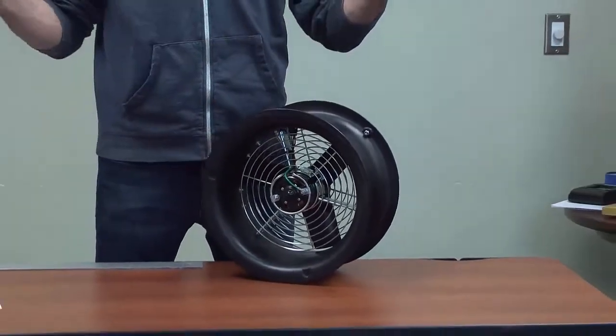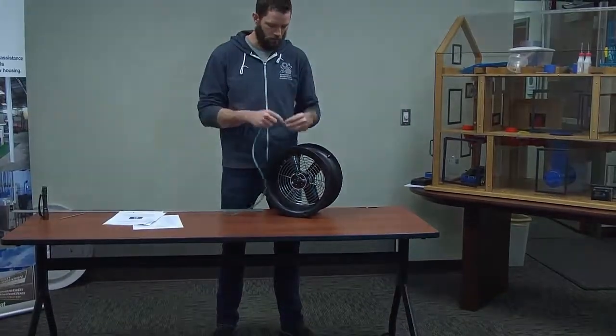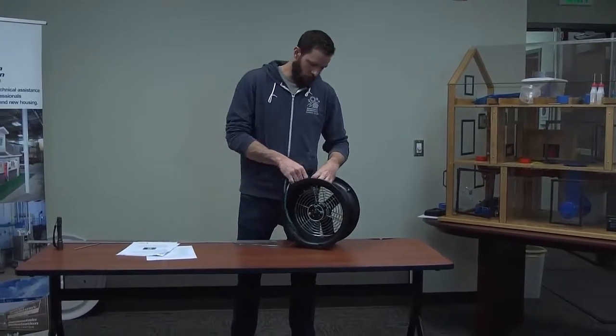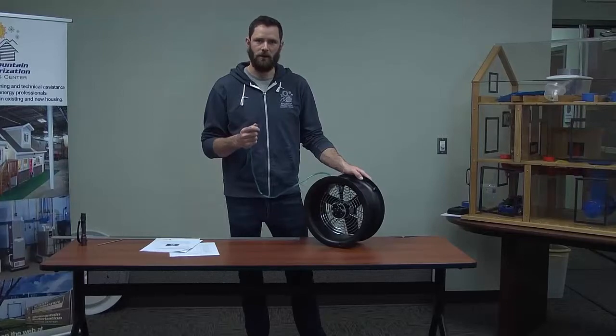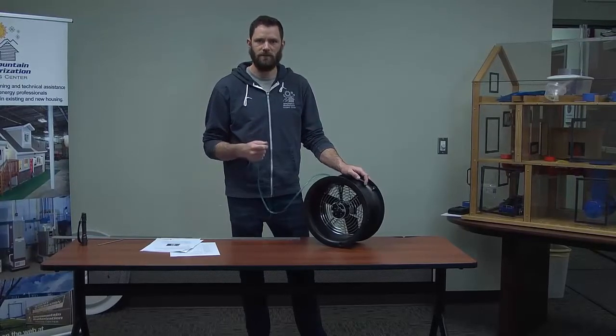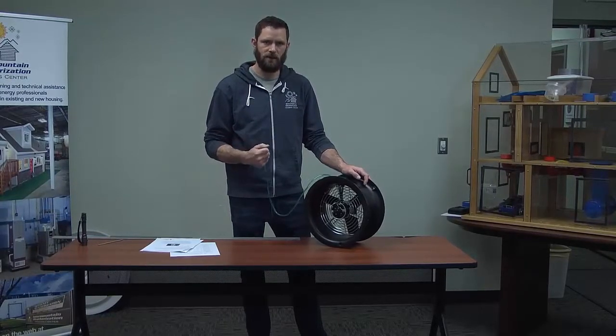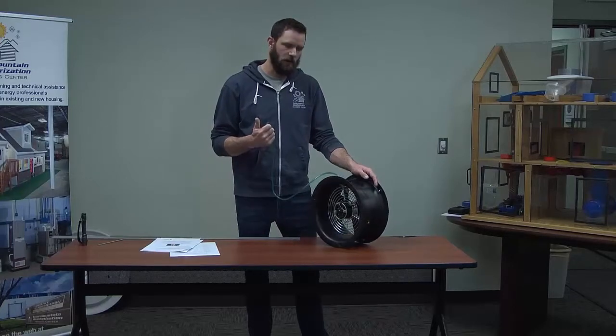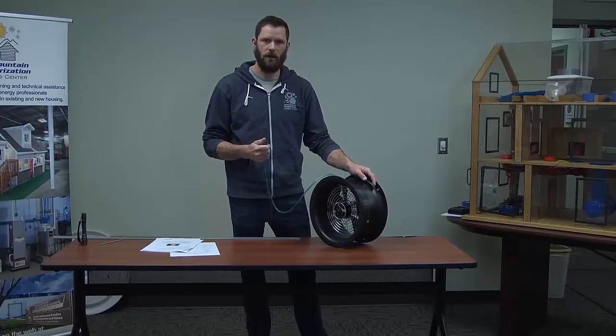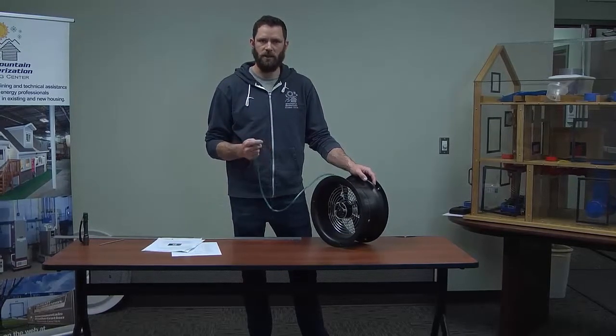We're going to take a piece of tubing, hook it to our flow port, and I'm going to create a vacuum again, and it should hold for 5 seconds. If it holds for 5 seconds, it passes that test. If it doesn't hold for 5 seconds, further inspection will be needed.